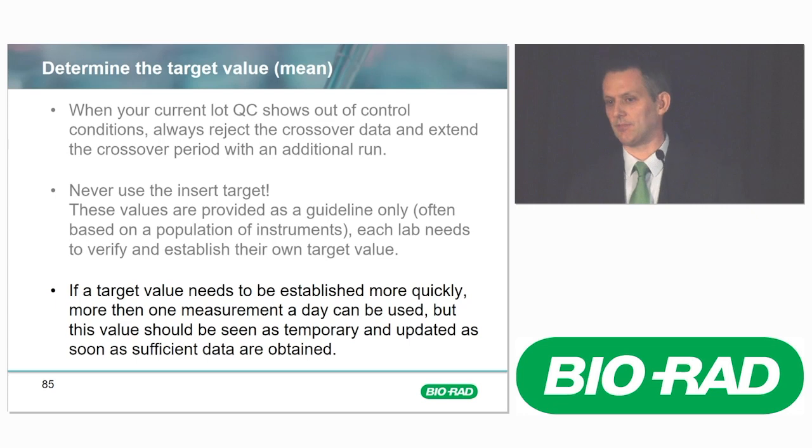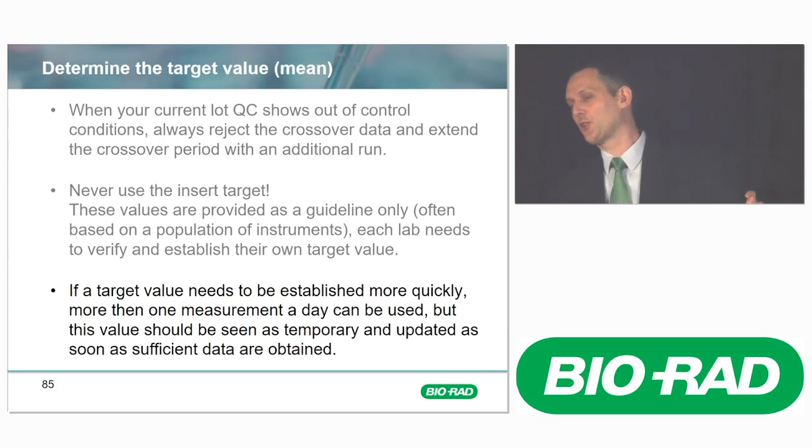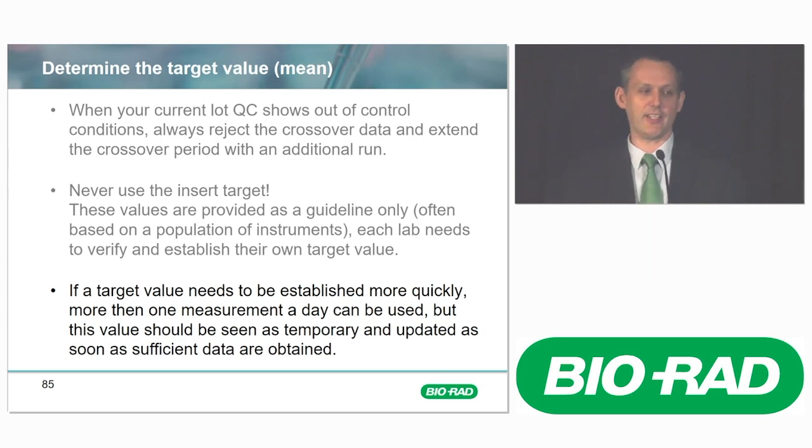If something happens, like I started by saying, if we take our box out of the fridge and we say, hey, last box, I also know labs that say, hey, last vial. So if that happens, then yes, unfortunately, you have to go a little faster with your crossover study, and you can do that. You can do multiple points a day. There are also other protocols like EP5 where I think it's 5 days with multiple measurements. So unfortunately, if things like that happen, it is statistics, it is numbers, so you could run 10, maybe 15, a bit more in one day.